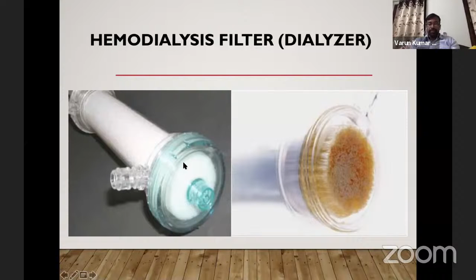What we do is we push blood this way, top to bottom, and dialysate fluid bottom to top. We put it in the opposite direction. Whenever there is opposite direction flow, there is better diffusion. The concentration gradient is maintained throughout the dialyzer, throughout the filter. So the blood goes here, the dialysate goes here, separated by a membrane. In blood, you can see toxins are highest here. Suppose creatinine is highest. The blood at the entry has the highest concentration of creatinine. This creatinine goes into the dialysate and this washes off. So all the new dialysate which is coming has low concentration of creatinine. Whichever is filled up here is taken off. So that way the concentration gradient is maintained.